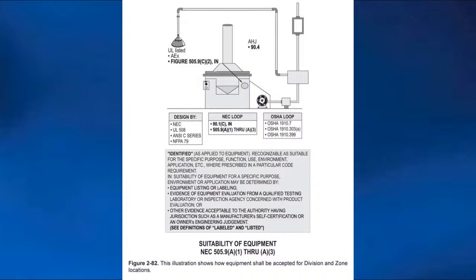A lot of electricians don't like the zones. For engineers, electricians, and inspectors, it's about how long the vapor can be there when you start reading through 505. If it's 1,000 hours or more, it's a zone 0.